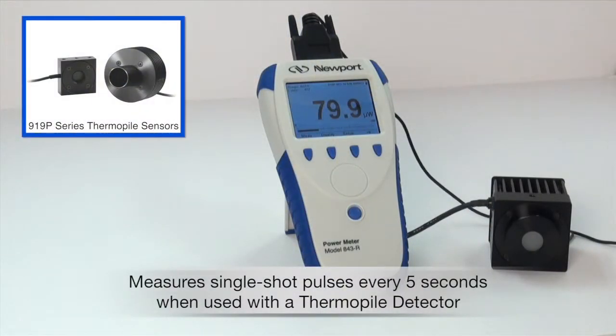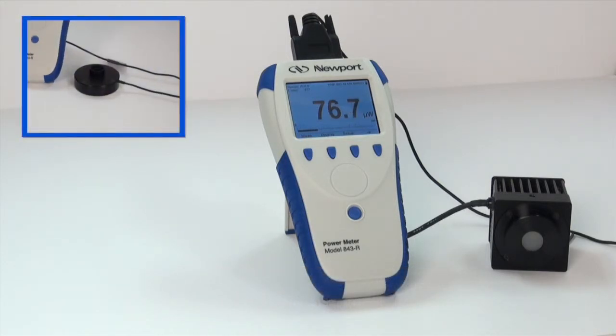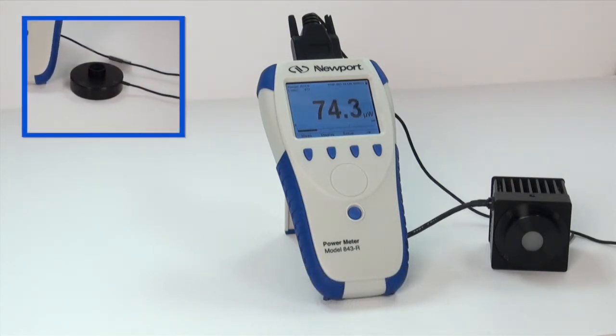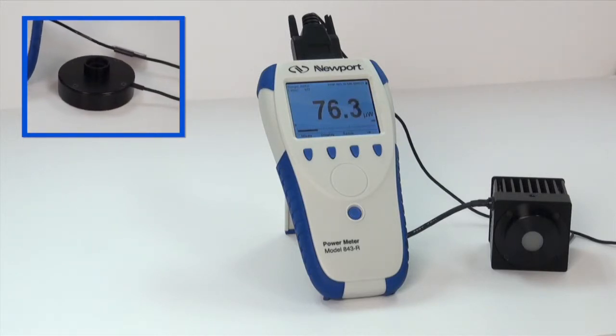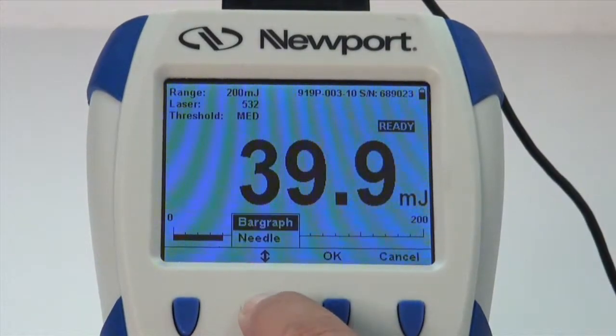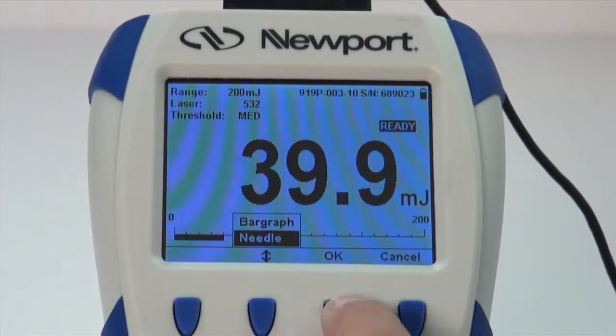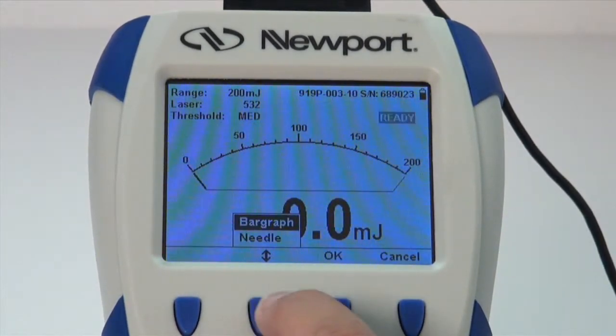The 843-R can measure individual, single-shot pulses every 5 seconds when used with thermopile detectors. To ensure the best measurement accuracy, center the laser beam carefully on the center of the active surface area of the detector. The laser beam should be at 90 degrees to the face of the detector. You have a choice of two different display modes for reading energy on an 843-R meter: numerical with needle, or numerical with bar graph.